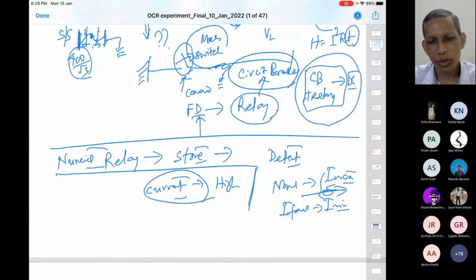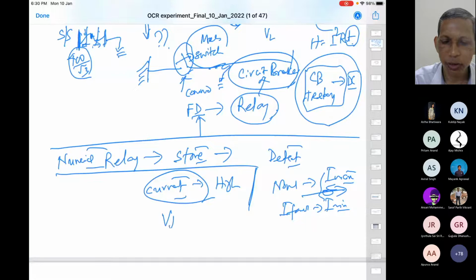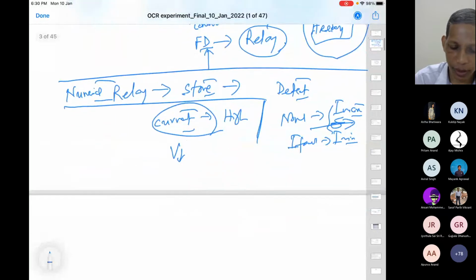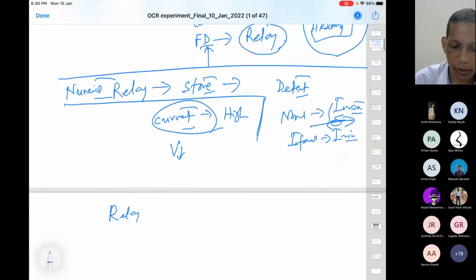Furthermore, whenever fault current becomes large, the voltage at different buses will be smaller because drops will happen across the system. At different points close to the fault, voltages will be down. So another indicator may be low voltage. A low voltage situation is also an indicator of this kind. These kinds of information features are used by different relays, and accordingly we have different relays in the system.